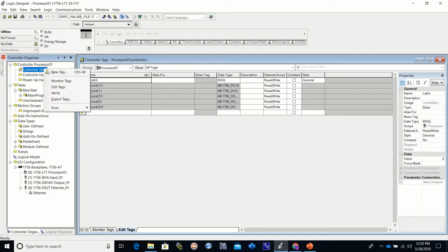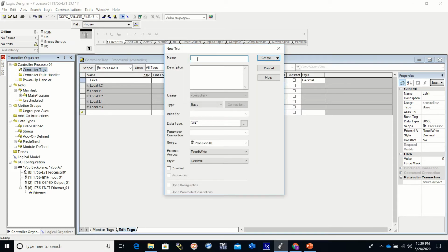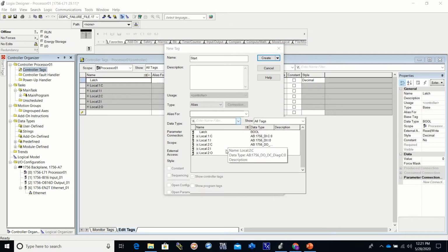And now I'm going to set up an alias tag. So again, left click, then right click. Some things are very common in about every program that you're ever going to see. We have a start. Usually a start button is a real world device. It's something that somebody can walk up and press. So this would be an alias. Start is alias for what? Well, it depends where you wired it to.